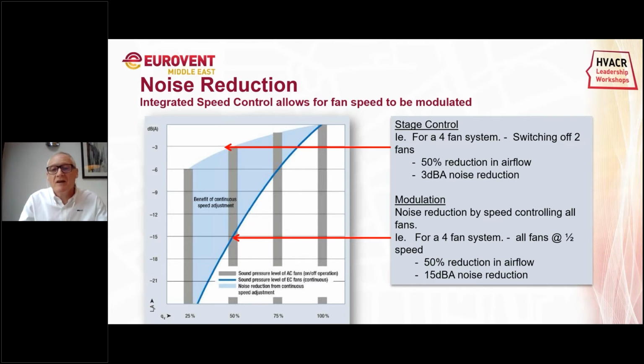With the EC fans, like I said before, we run them all at 50% speed. So for a 4-fan system, if we run them all at 50%, you'll get the same 50% reduced airflow. That will give you a 15 dBA noise reduction. There are a lot of convenience stores and quite a few supermarkets now situated in residential areas. That 15 dBA noise reduction, especially at night, is a huge difference. And hopefully all the residents that live close to the supermarkets will be able to sleep without any noise disruptions.